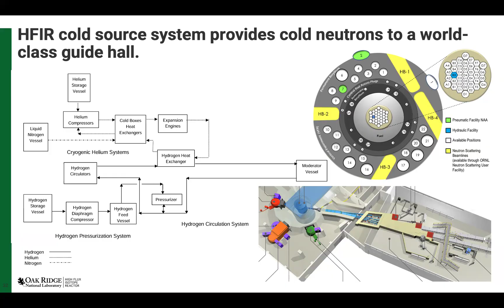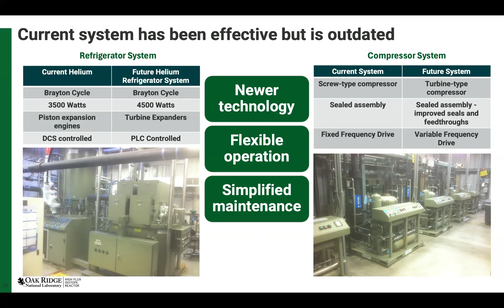This shows some before and after of the refrigerator system. We're going to increase its capacity from 3,500 to 4,500 watts, and change it to a regular PLC controlled system, so we can find instrument controls people who can program it, unlike the current one which is very difficult. The new one goes from a screw type compressor to a turbine type compressor, with variable frequency drives, and sealed. Right now oil contamination is a huge problem, but that will be a thing of the past with the new system. So we're simplifying across the board.